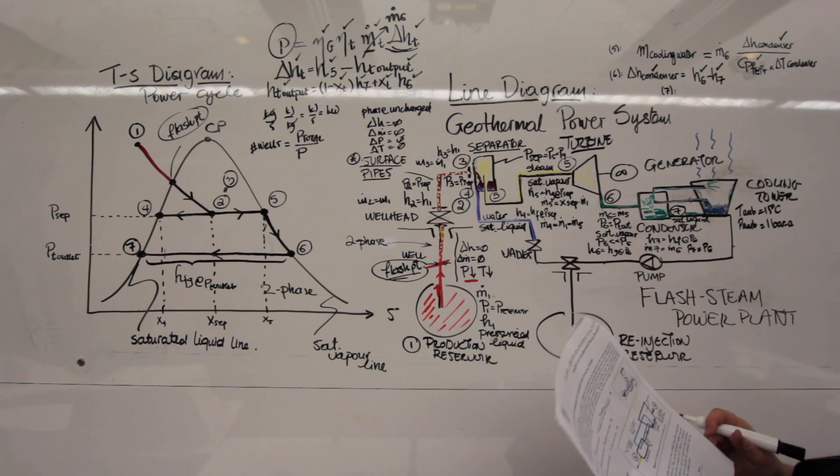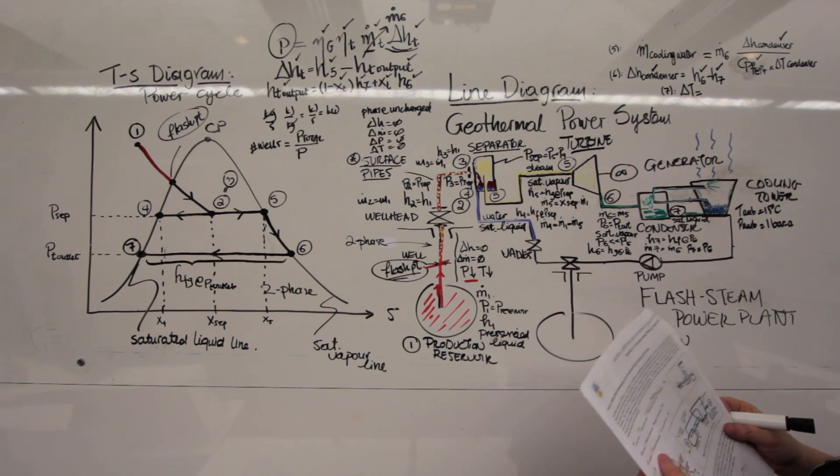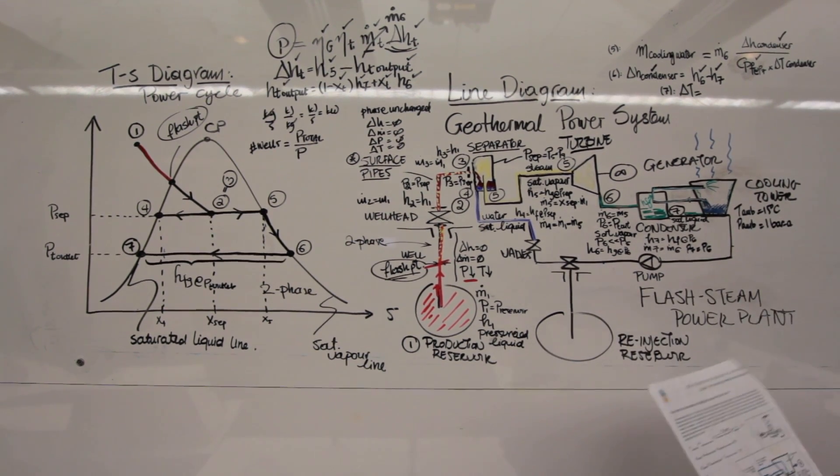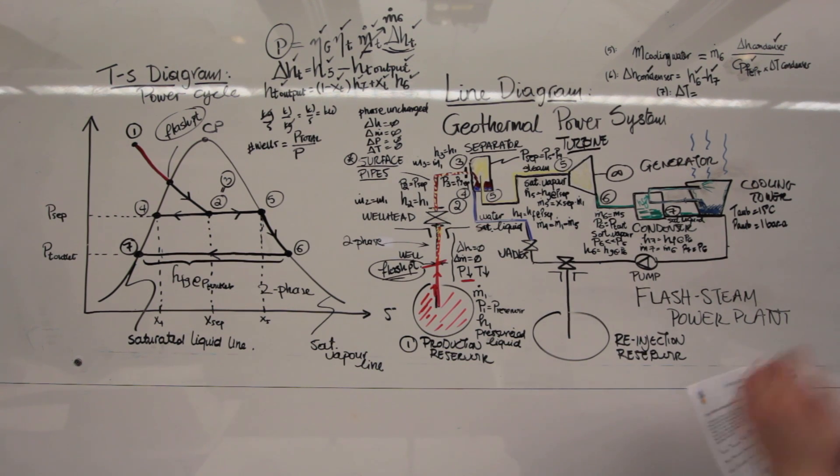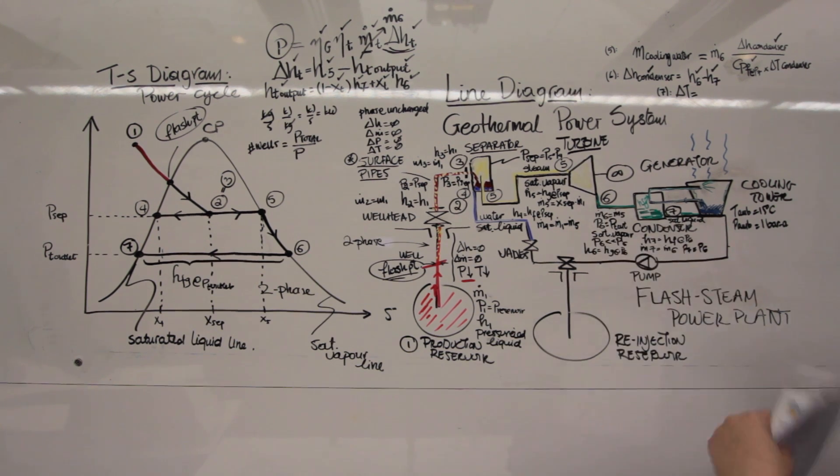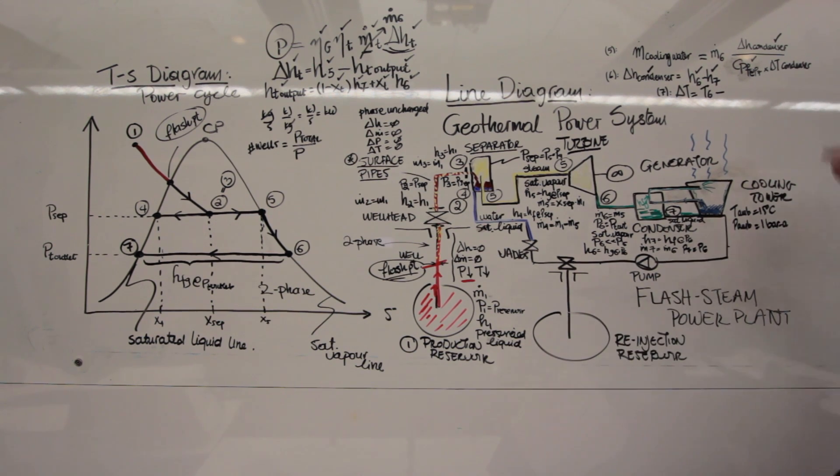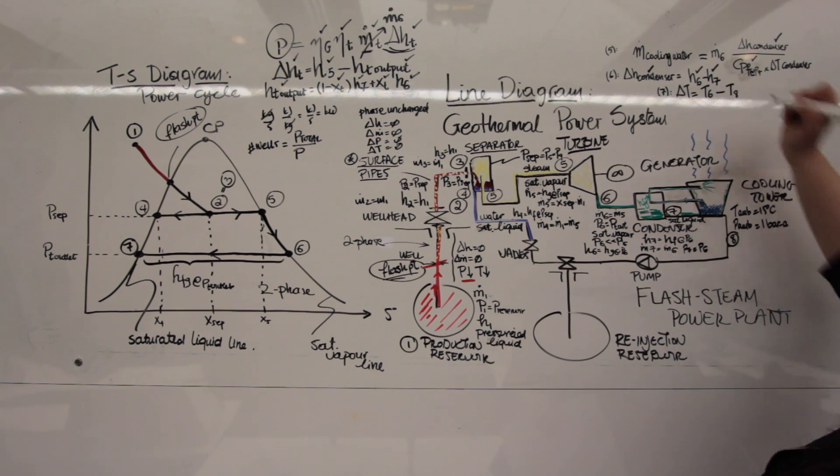And from equation 7, then we get that delta T is equal to T at the steam turbine outlet. Now that's a tricky one. We have a steam turbine outlet, right? So it would be at 6. So it will be T6 minus T at the cooling water outlet. Cooling water outlet. We assume that's at ambient conditions. So that would be T at 8, right? This is equal to 15 degrees C.